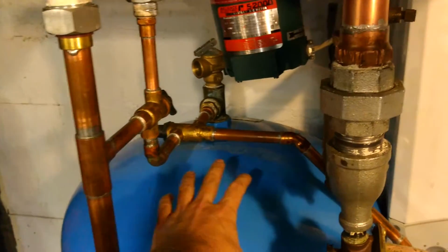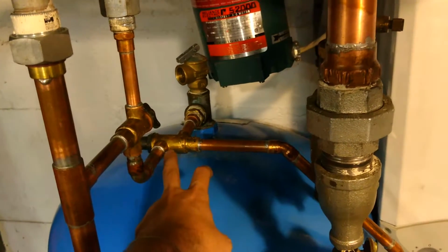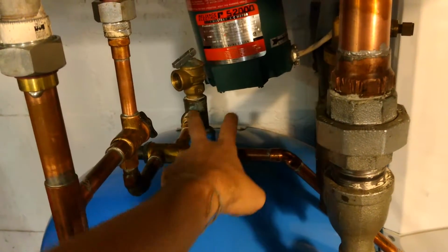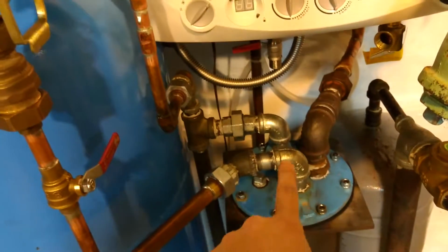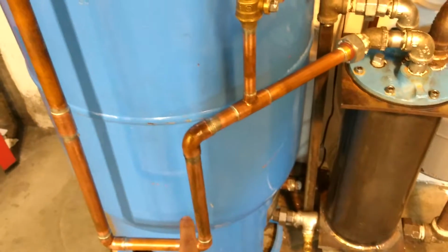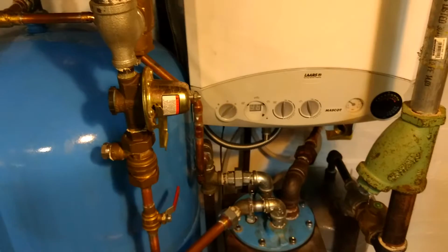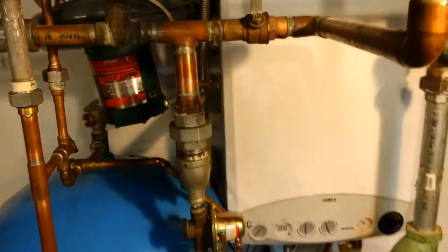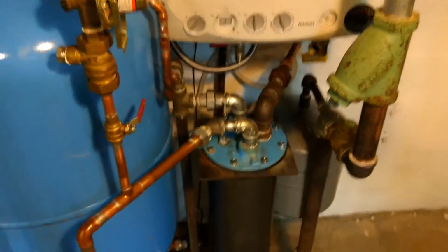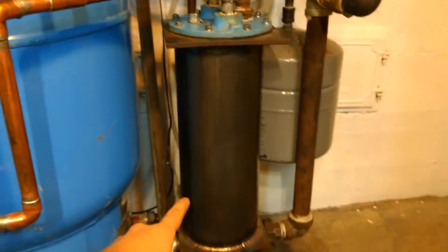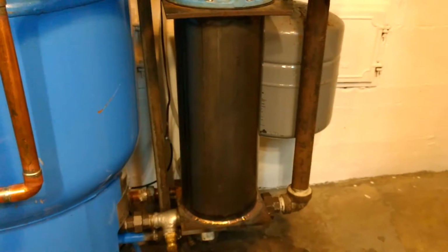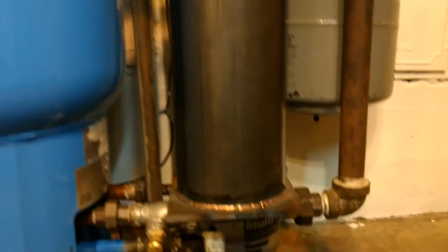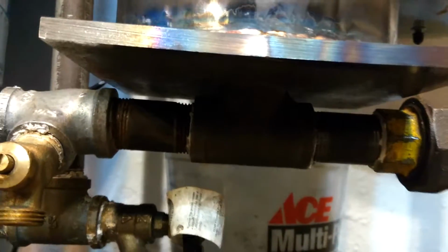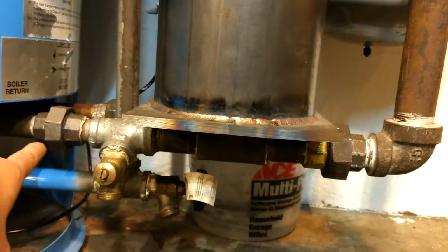And if the case is that this tank temperature is below the set point of this thermostatic valve, therefore it's going to be wide open to just the hot water, then I'll still get heat recovery, but it will come from the bottom to the bottom of this tank, and I'll still have that huge temperature differential. So no matter what, I'll have as efficient of a system as I can get. The heat exchanger tank I made was just a piece of, I think it was 7-inch OD, something the local shop had. And then I just welded a plate on the top and bottom, cut a hole in the top, and then on the bottom I welded just a T, and that's where it comes in from the house on this side and from the hot water return on that side.